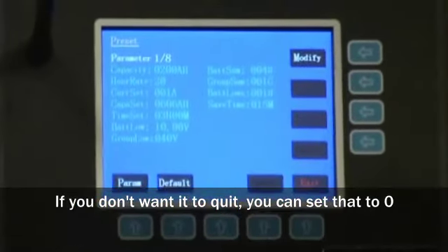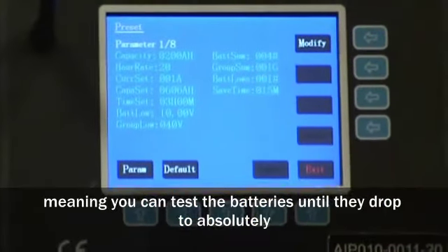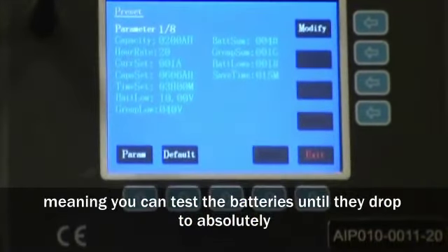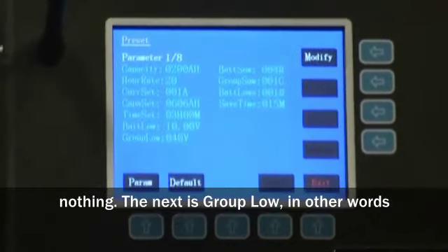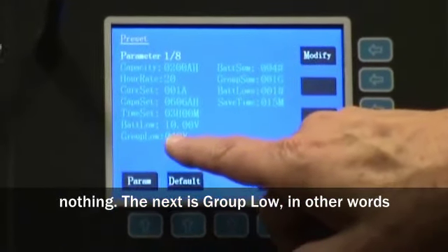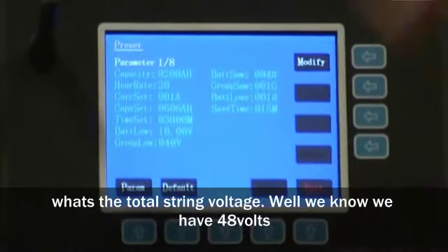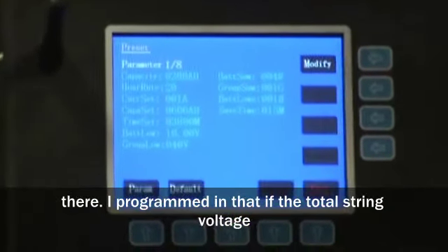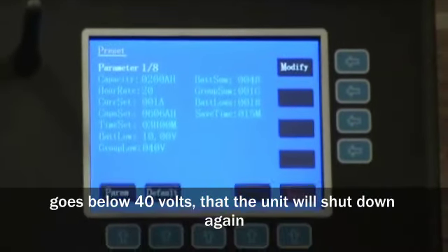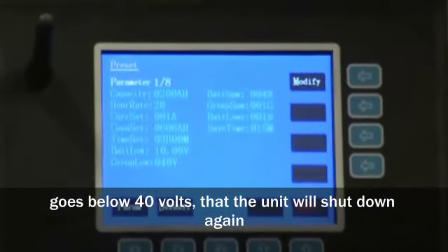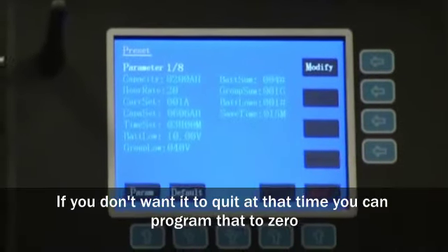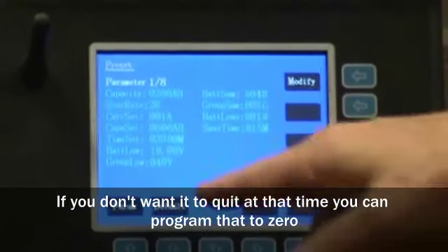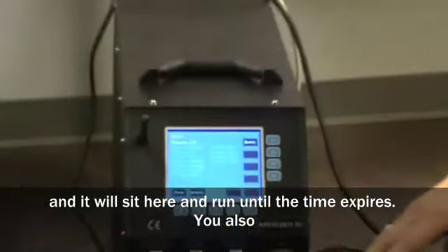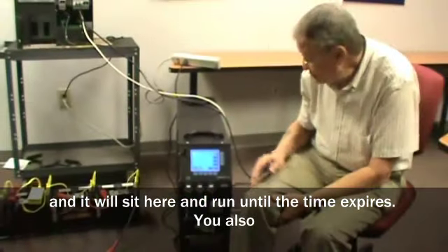If you don't want it to quit, you can actually set that to 0, meaning that you can test the batteries until they drop to absolutely nothing. The next setting is group low. In other words, what's the total string voltage? Well, we know we've got 48 volts there. I've programmed in that if the total string voltage goes below 40 volts, that the unit will shut down. Again, if you don't want it to quit at that time, you can program that to 0. And it'll sit here and run until the time expires.